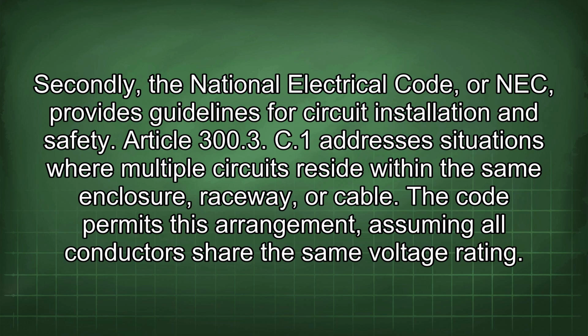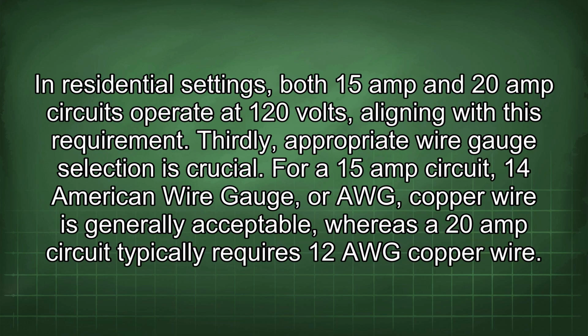Secondly, the National Electrical Code, or NEC, provides guidelines for circuit installation and safety. Article 300.3 C1 addresses situations where multiple circuits reside within the same enclosure, raceway, or cable. The code permits this arrangement, assuming all conductors share the same voltage rating. In residential settings, both 15 amp and 20 amp circuits operate at 120 volts, aligning with this requirement.